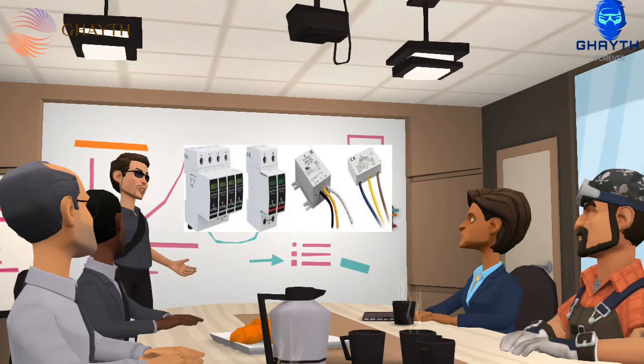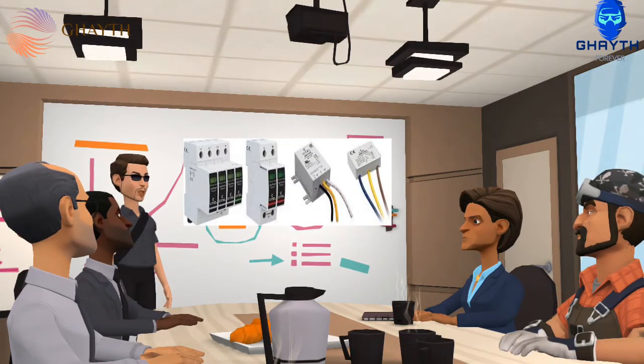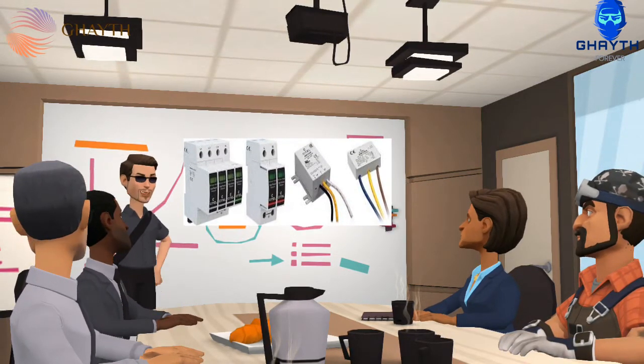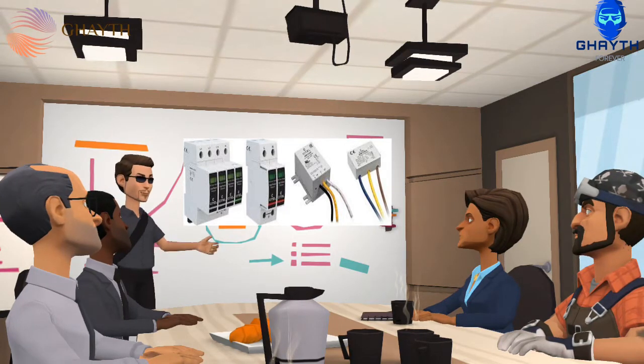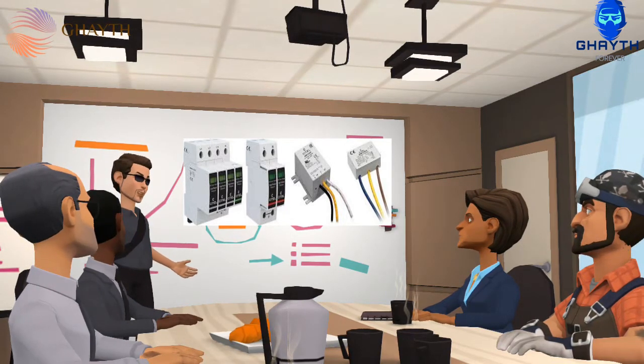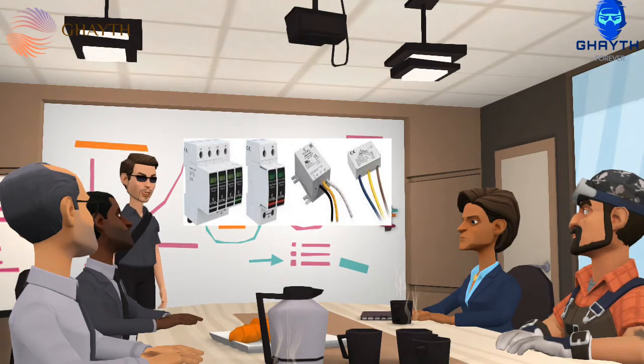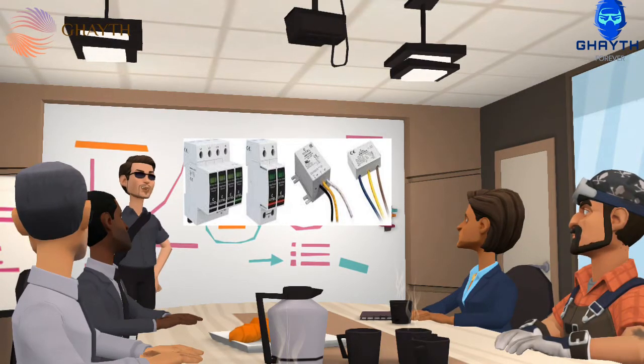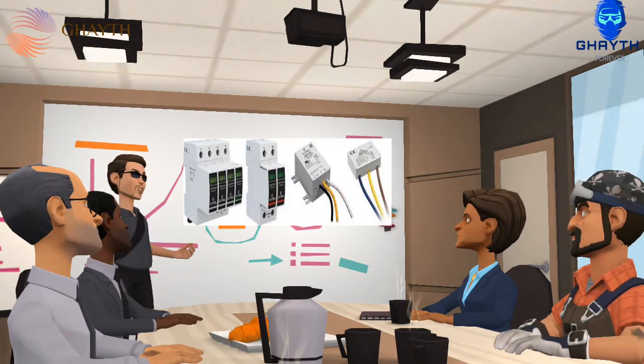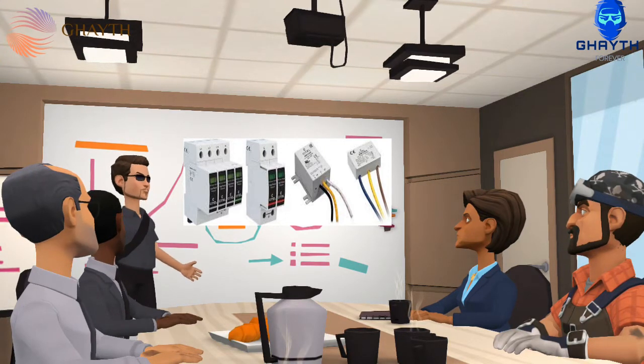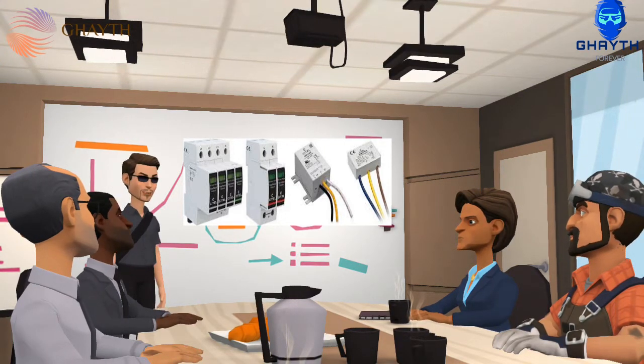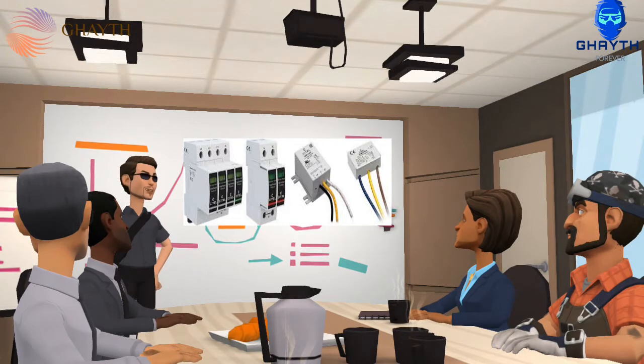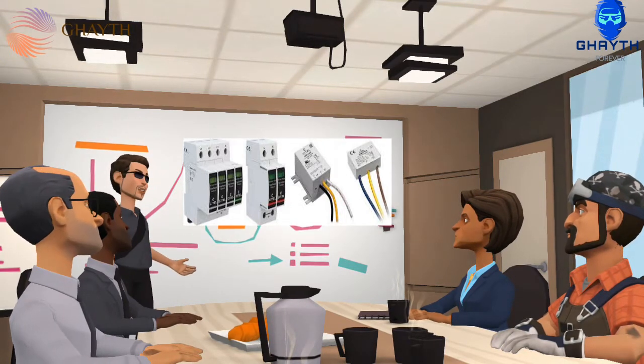A voltage spike is a transient event, typically lasting 1 to 30 microseconds, that may reach over 1000 volts. Lightning that hits a power line can give many thousands, sometimes 100,000 or more volts. A motor when switched off can generate a spike of 1000 or more volts. Spikes can degrade wiring insulation and destroy electronic devices like battery chargers, modems and TVs.